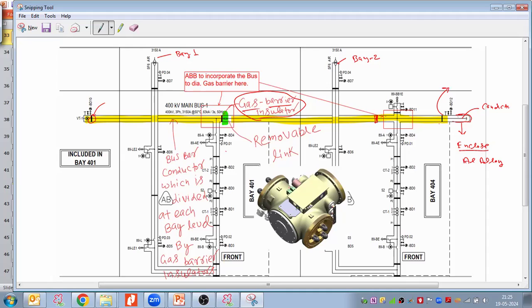Then only can I say that the bus bar will be divided at each bay level. Now, if they do not provide it, the bus bar is divided here and then comes over here. It would be better if they provide it here, so that from here to here there would be one separate gas section. If we need to do any kind of maintenance here, there is no need to degas this portion of the bus duct or bus bar. Only here and here we have gas barrier insulators, so just these portions need degassing and we can do the maintenance. There would also be some saving in the SF6 gas. So that is the comment I gave to ABB, this was the ABB make GIS.